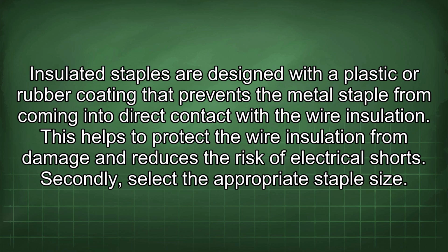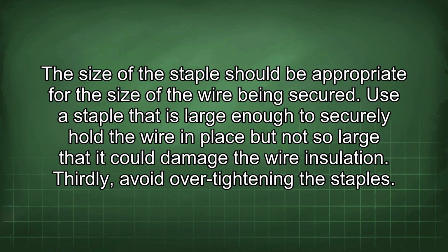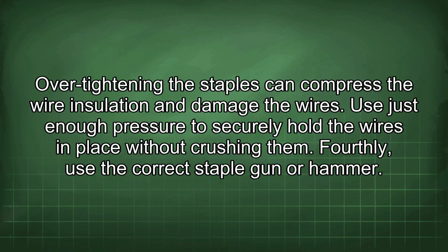Secondly, select the appropriate staple size. The size of the staple should be appropriate for the size of the wire being secured. Use a staple that is large enough to securely hold the wire in place, but not so large that it could damage the wire insulation. Thirdly, avoid over-tightening the staples. Over-tightening the staples can compress the wire insulation and damage the wires. Use just enough pressure to securely hold the wires in place without crushing them.